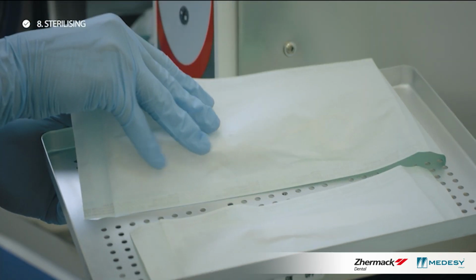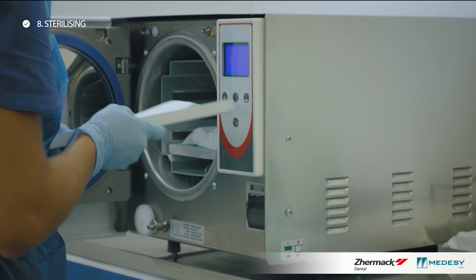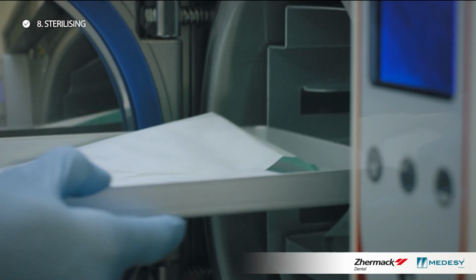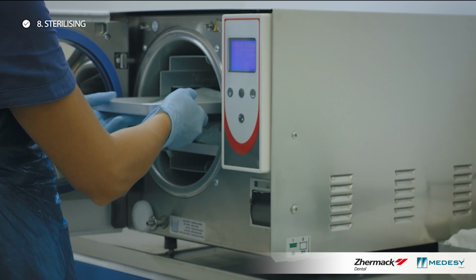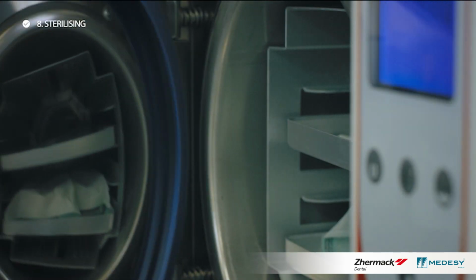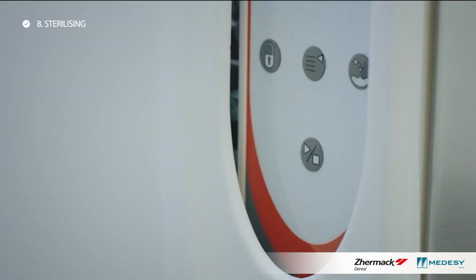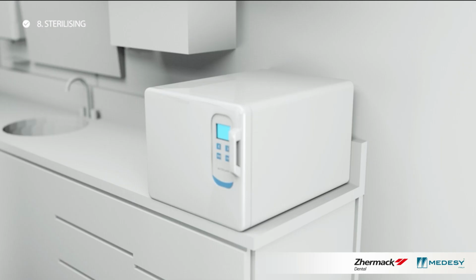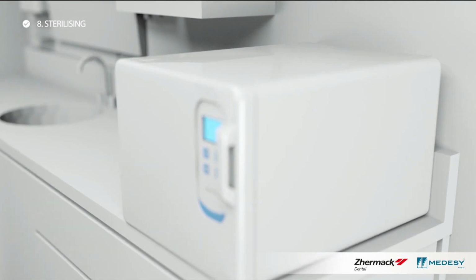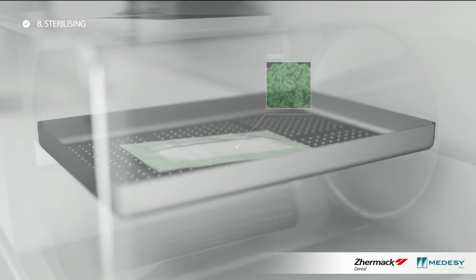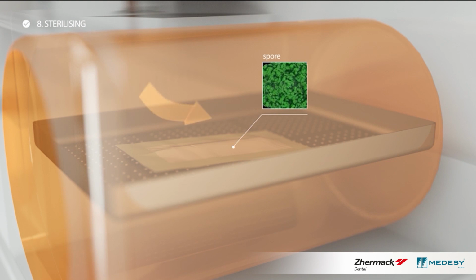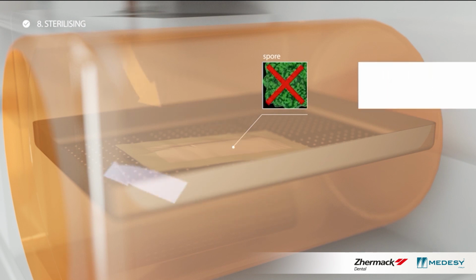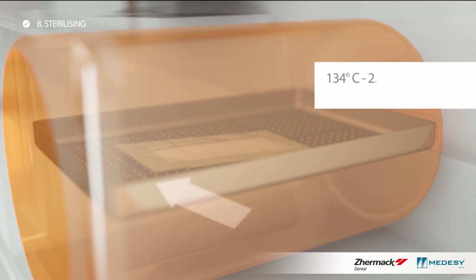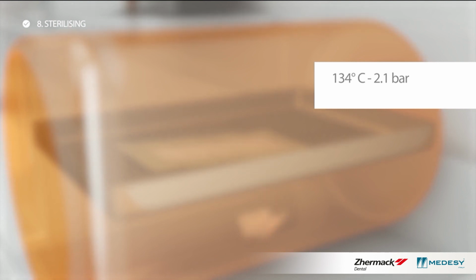The pouches must be placed in the trays next to each other with the paper side facing up and with no overlap. The trays must be placed in the autoclave, non-overlapping or masked. To sterilize surgical instruments, we suggest using a Class B fraction vacuum wet heat autoclave. We recommend sterilizing instruments at 134 degrees at 2.1 bars or 121 degrees at 1.1 bars.